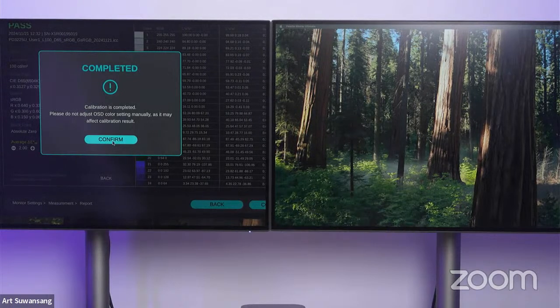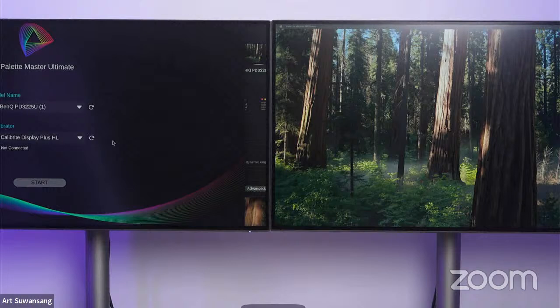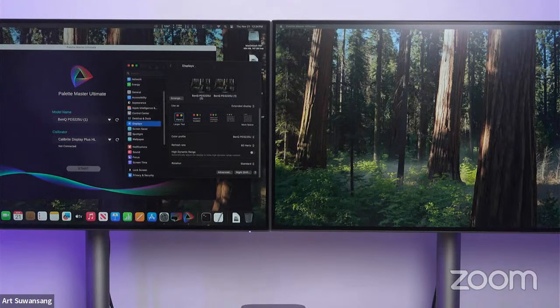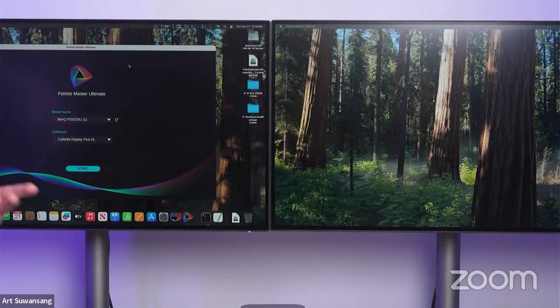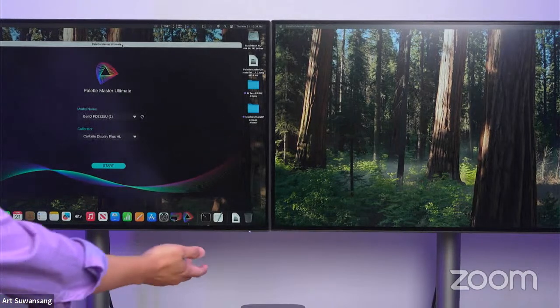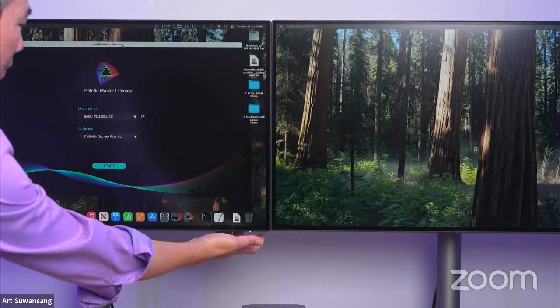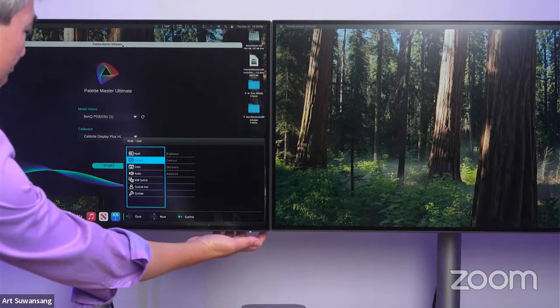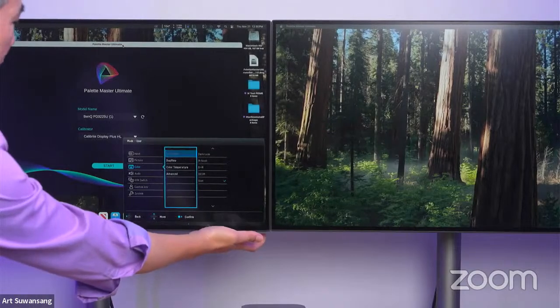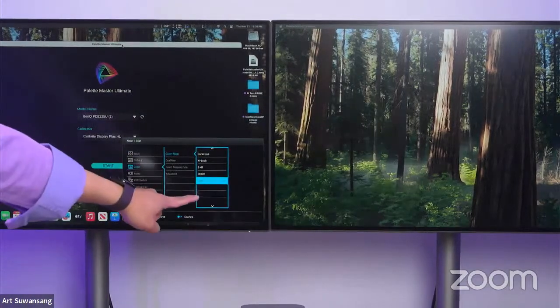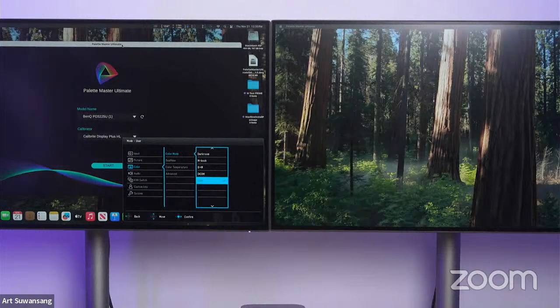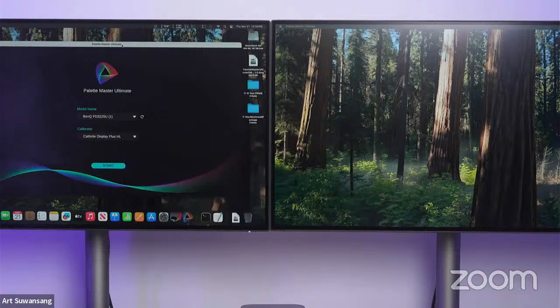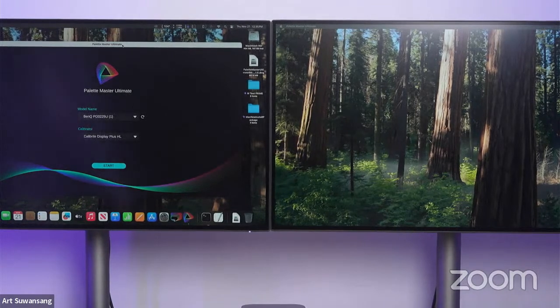So I'm going to confirm this, but the whole reason behind this is because this is not a hardware calibration. It doesn't write this into a hardware calibration slot. What it does is it writes all this calibration data, and you're going to probably see this, into the color mode called User on the display, as you see right now. So it's not necessarily writing into a LUT per se, it's just writing into the User slot, which is specifically designed to store this calibration data. But again, I can still go in and change the brightness on the display. It's something that I don't recommend doing.